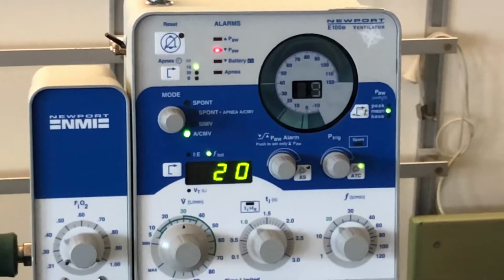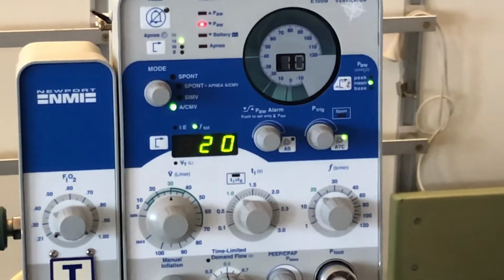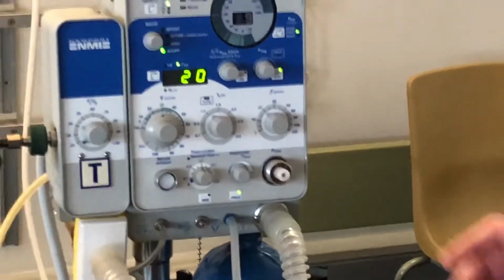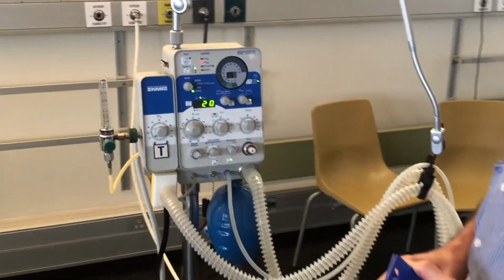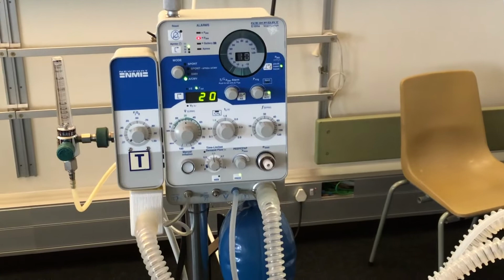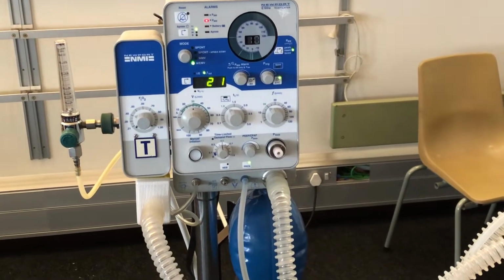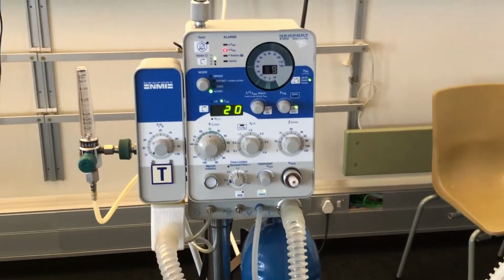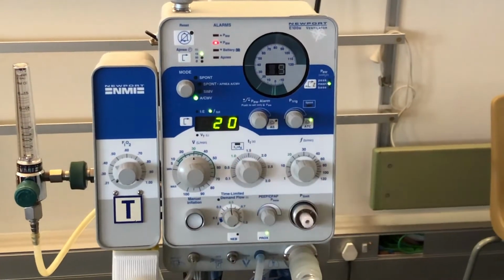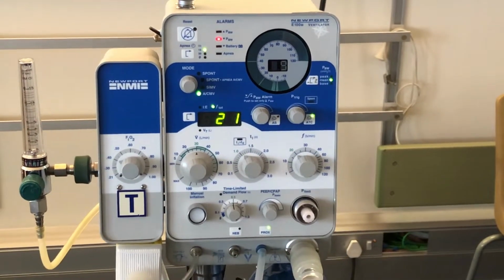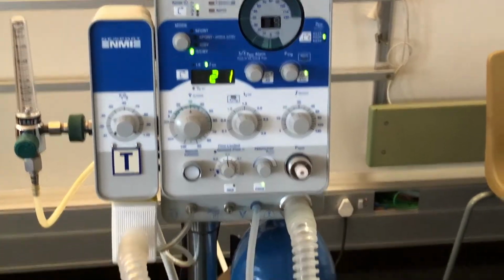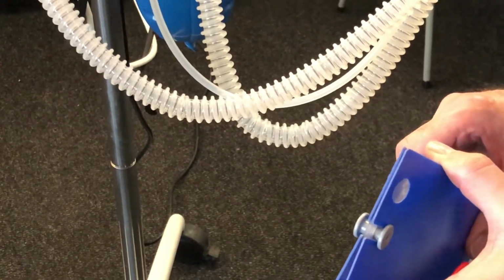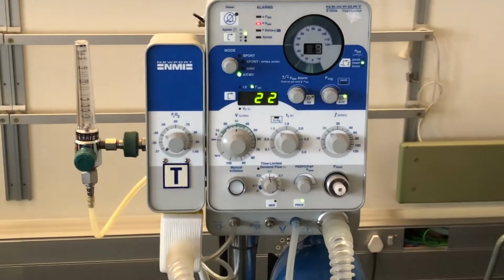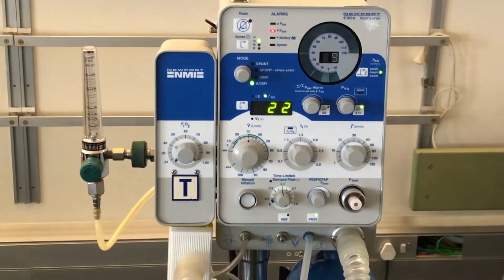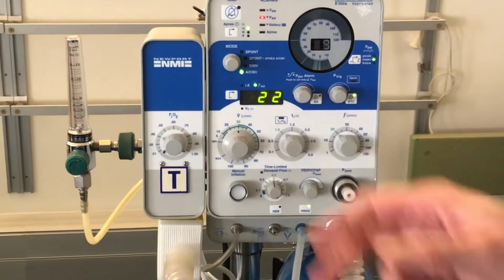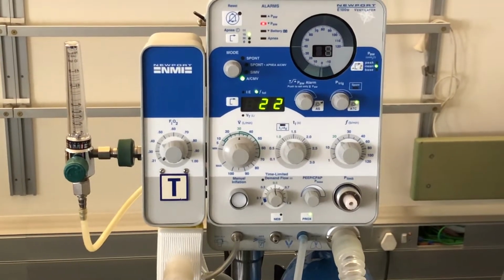So I'm just going to fiddle with the bag on the end here just to try and mimic some patient breaths. And if you look here now, you'll see the spont light up, and that's the machine thinking it's detecting a trigger. And every time the machine detects a trigger, it delivers a preset breath. So if I try and trigger the machine a little faster, and you look at the respiratory rate there in the respiratory rate panel, you'll see it's risen above 20 now. So the machine is giving additional breaths in response to my triggering.